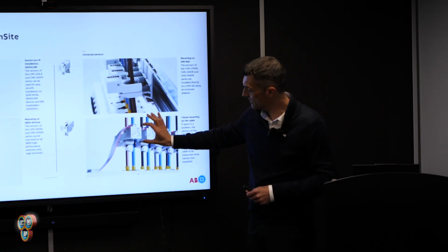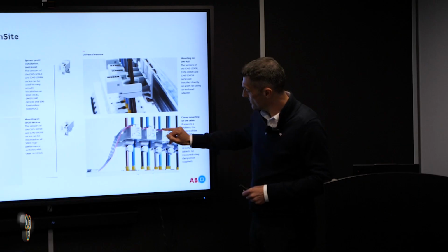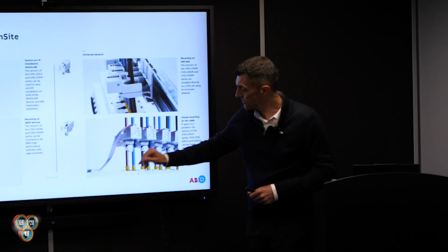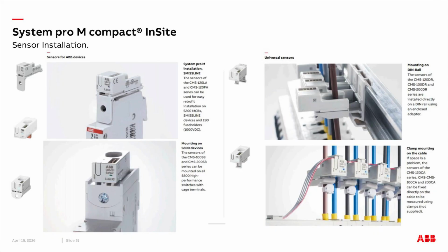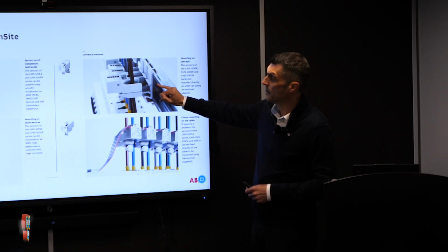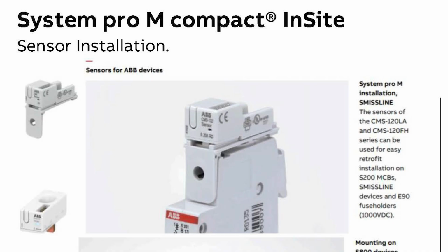So it's the sensor there that goes over the load. You can see the ribbon cable which comes back to the control unit. There's a cable tie variant, and there's also a DIN rail version as well. And over and above that, there's an open core sensor, and we also do a closed core version as well.